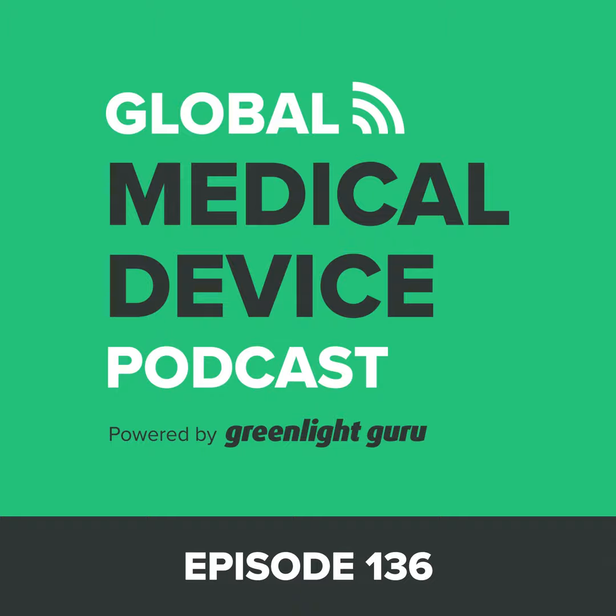It uses what's called the eSubmitter software, which is more robust. I have been involved with this. It's more robust than simply the eSTAR PDF format. But there are some limitations for the Quality and 510K Review, namely that it's limited only to devices that use what I call well-established technologies.